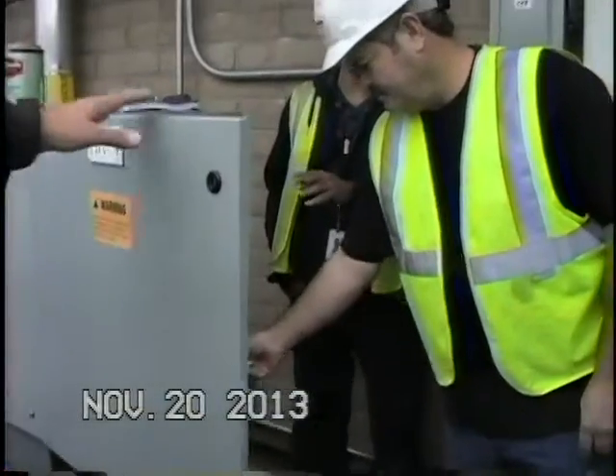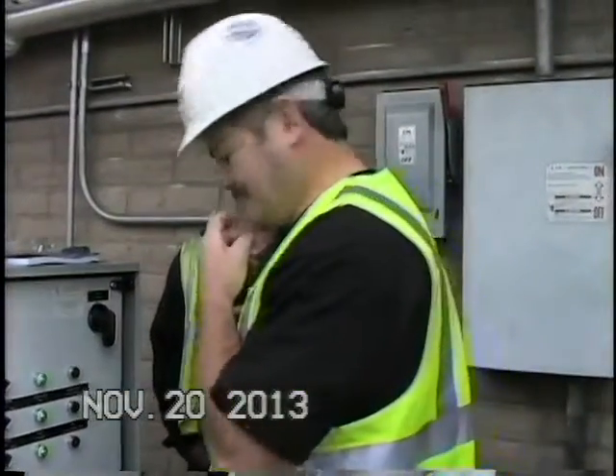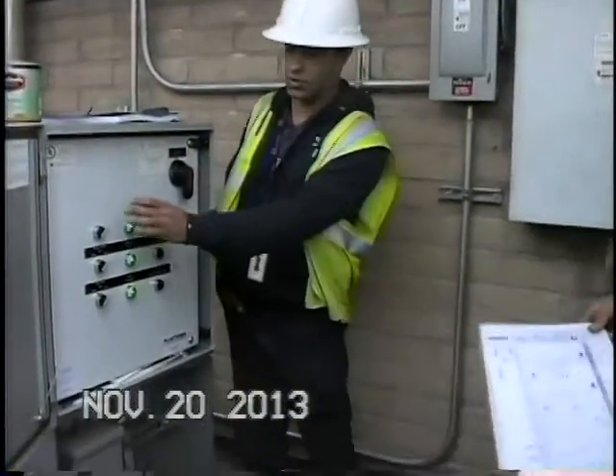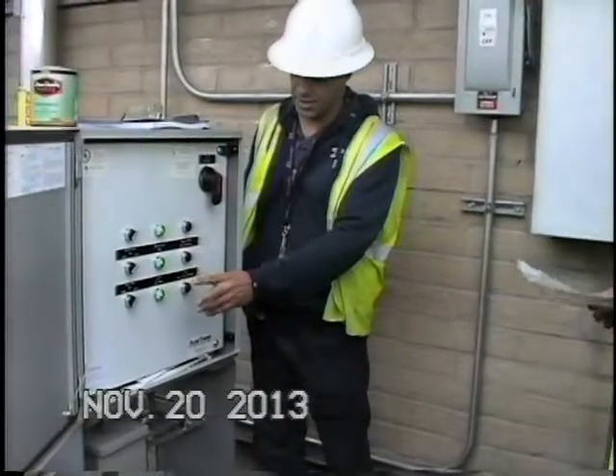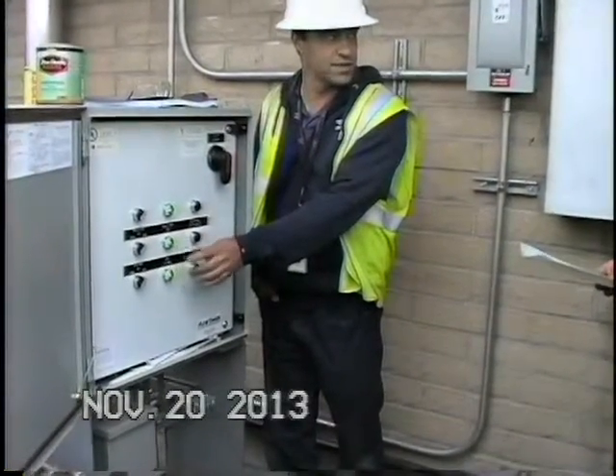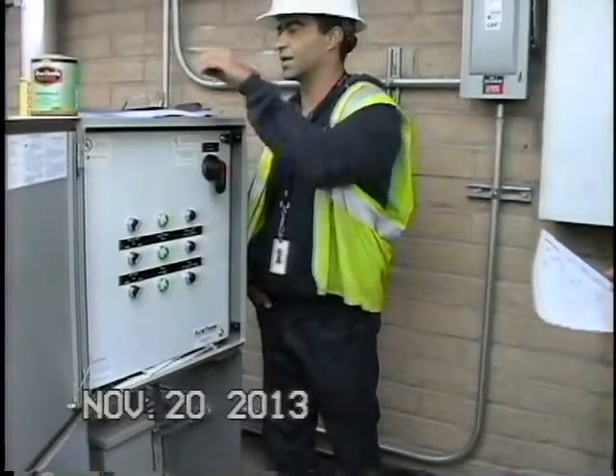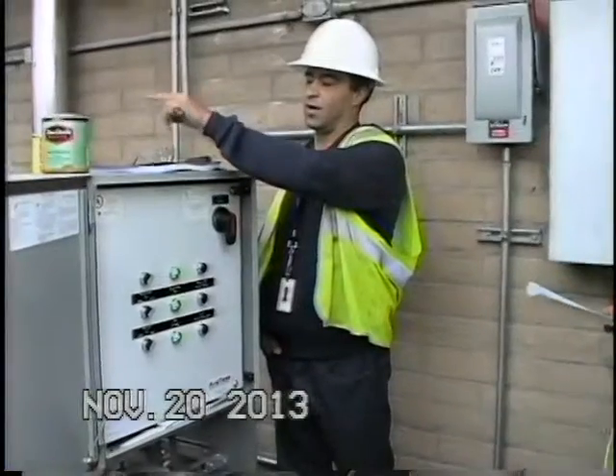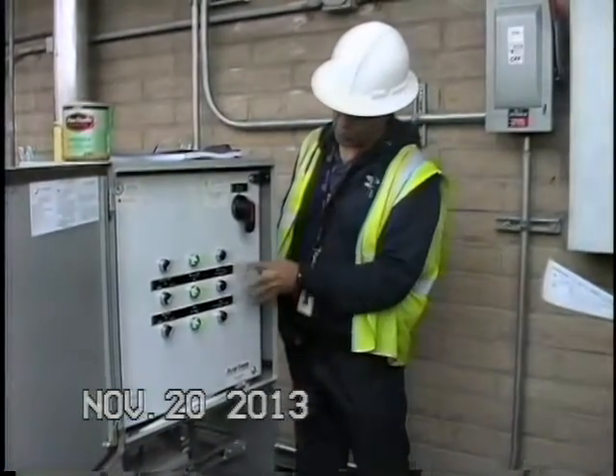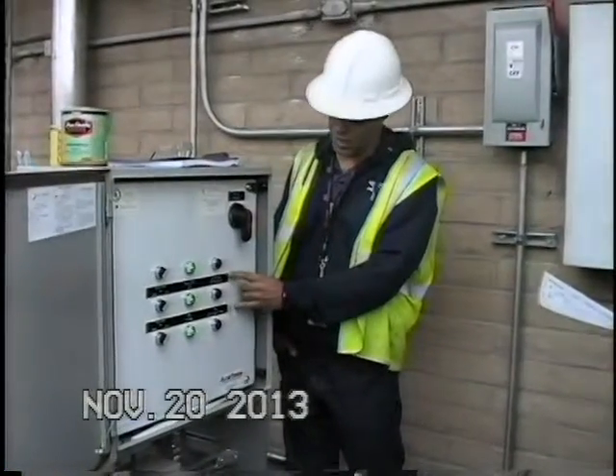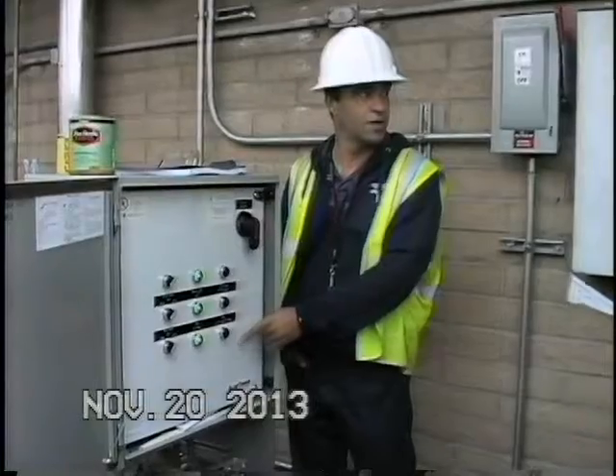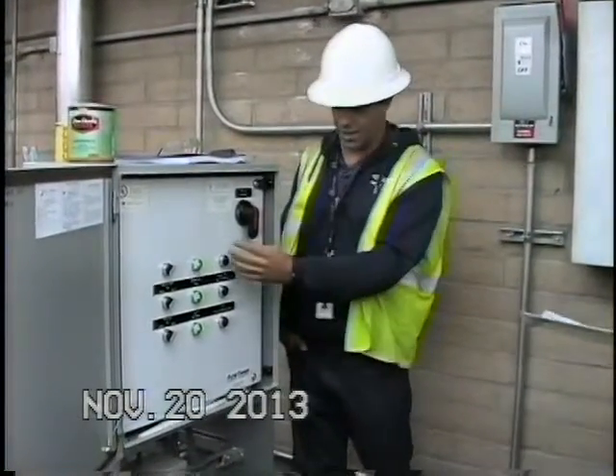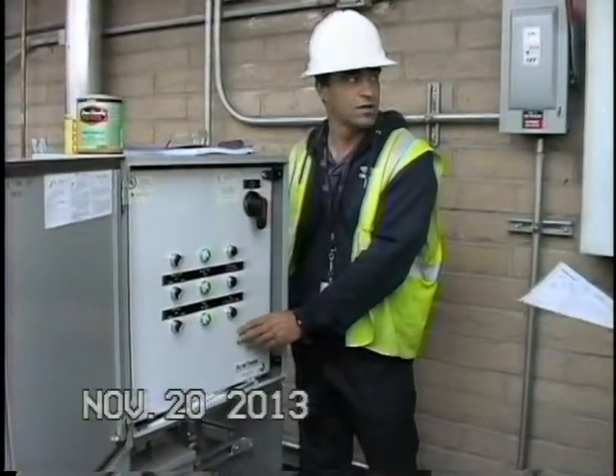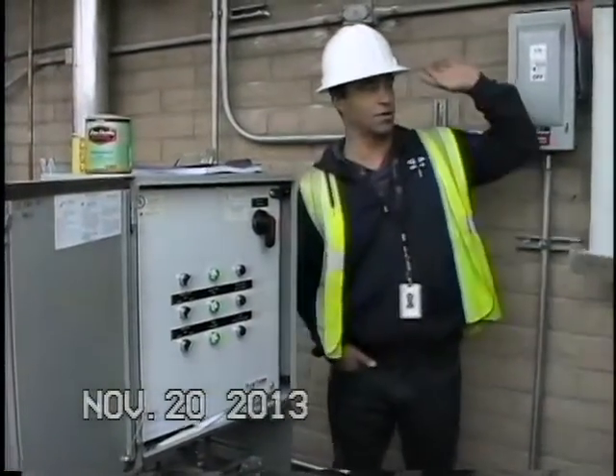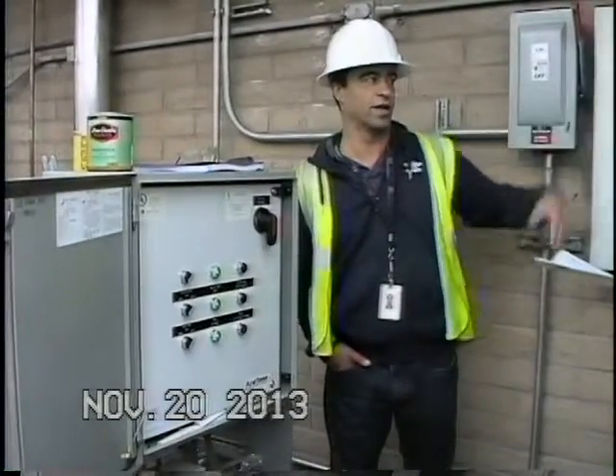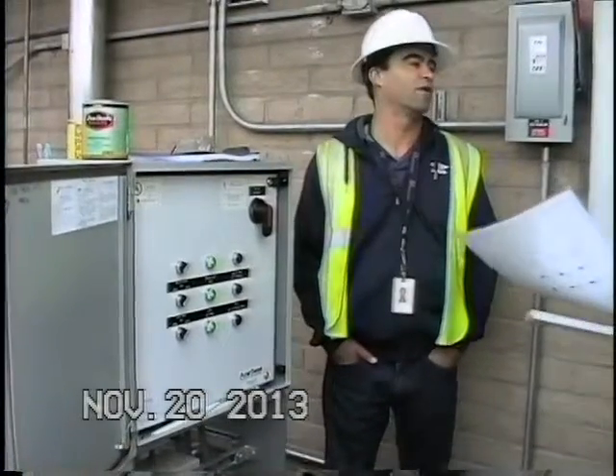Just a quick word on the way Johnson is managing: it's just sending it a start signal. We're closing the start, and we're getting a pump status from it. Two pump statuses: the loop status and the primary pump status for the boiler. And we're getting one alarm signal. Even though you've got individual alarm signals here telling you what went off, at the EMS panel we're only receiving one. They're all run in parallel. So any alarm trips here will signal an alarm on your Johnson panel, which we'll go over later with Johnson. Boiler fault in there? It just says boiler fault. That's all.